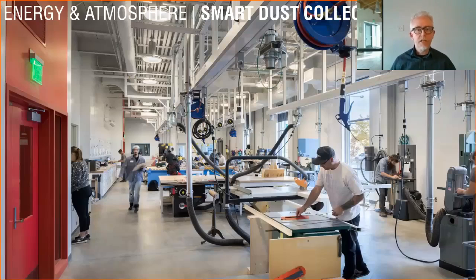Another example of optimizing a building system is the dust collection system. Traditionally these systems run at 100% capacity whether there's one piece of equipment running or ten. Here at the Aerospace building, it's a variable air volume system, meaning it ramps up gradually as more equipment is turned on.